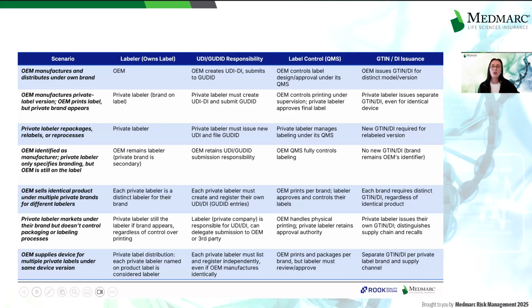If the private labeler is involved in repackaging, relabeling, or reprocessing activities, they are considered to, quote unquote, own the labeling and are also responsible for UDI and GUDID registration. When the same device is sold under a different brand, a unique global trade item number, or GTIN, must be assigned. Typically, the private labeler will be responsible for this. This enables the private labeler to manage product tracking across distinct supply chains, monitor inventory, and conduct targeted recalls if needed. However, the decision regarding the labeling responsibility may vary depending on the desired ownership of the market. With that in mind, the next topic we'll explore is how to clearly define roles and responsibilities within the private label relationship.